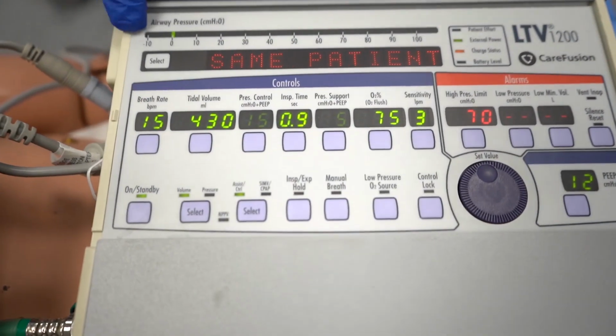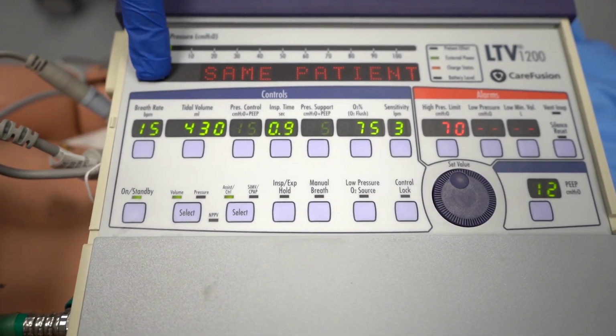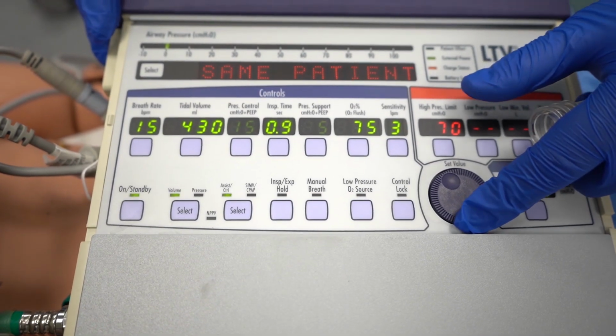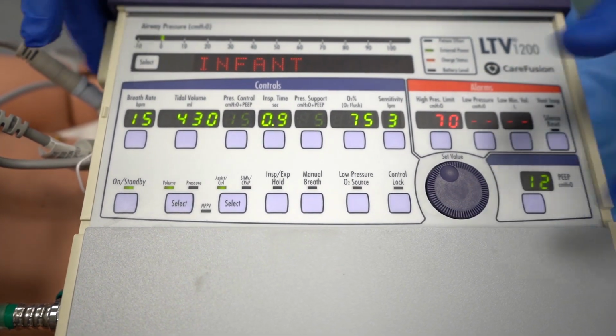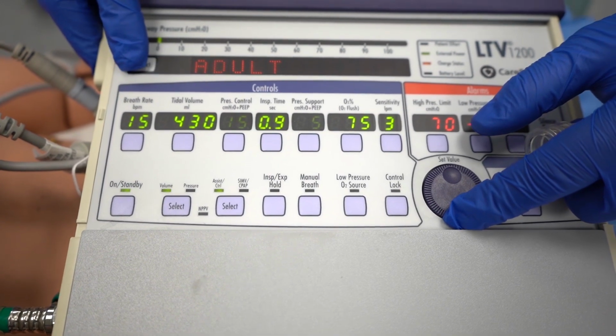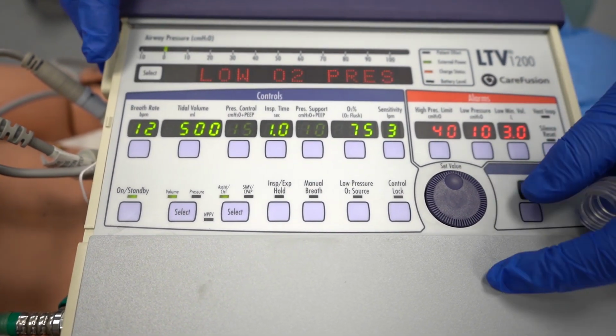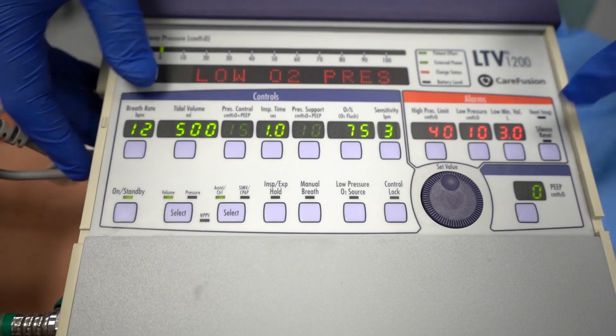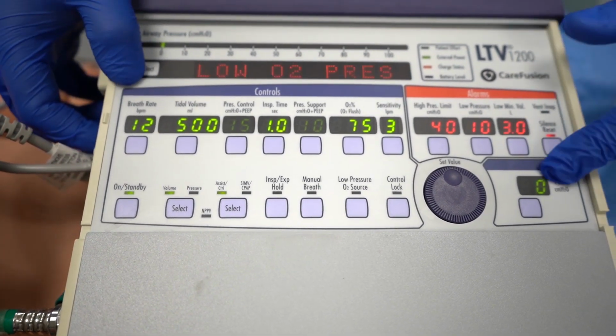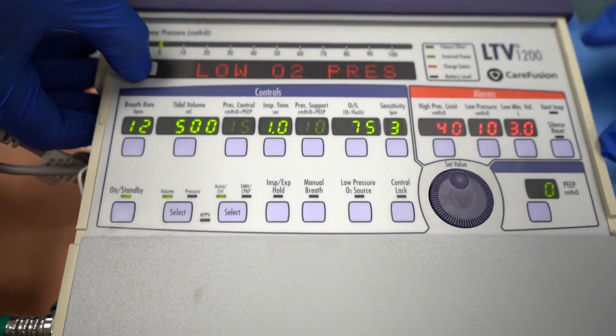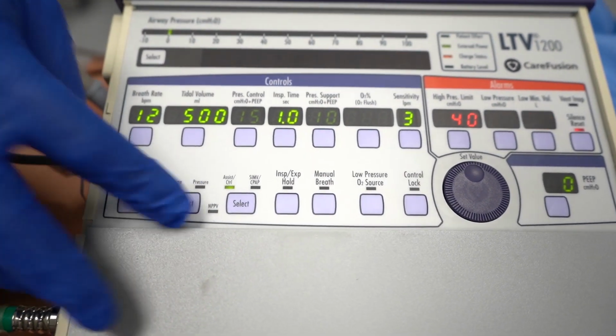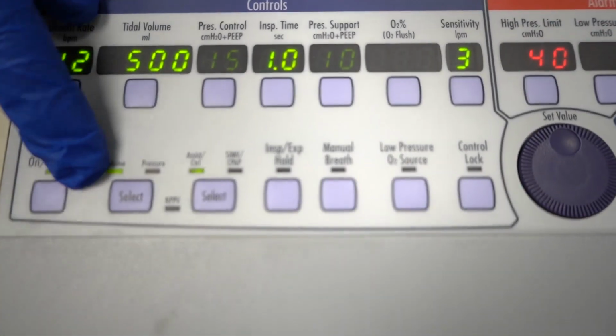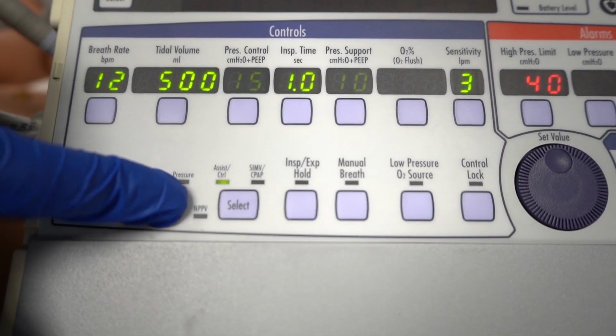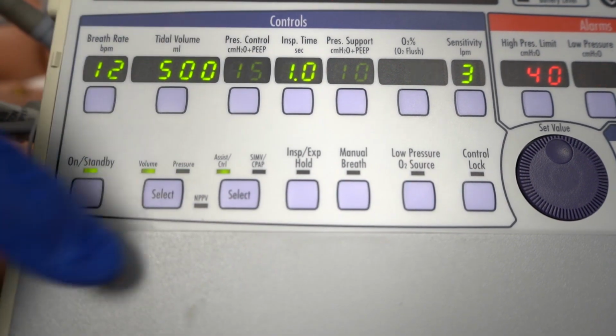Alright, so once the ventilator is on, you're going to hit select same patient. So same patient or new patient. You're using the dial down here, so let's say new patient. You're going to select adult, pediatric, or infant, so we'll select adult. This alarm is because I'm not plugged to oxygen. Your modes are located on the bottom. You either have volume control or pressure control. To select the mode, you just hit select, wait till it's blinking, and then hit select again to change the mode.